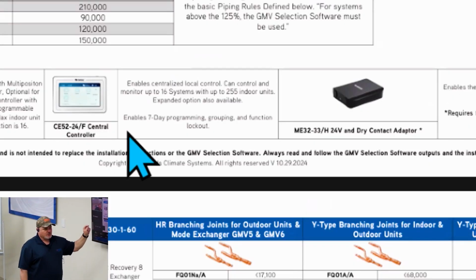Then with your daisy chain wiring between G1 and G2 between those 3, if you've already got those dip switches set, when you commission and start up those units, it's already going to automatically not duplicate addresses on your indoor units. So when you come back and hook up that central control or Cool Automation, it'll automatically be able to pull all those addresses in, because these are self-addressing, and you won't have a mode conflict. If you don't do that ahead of time, now we have to go back, shut everything down, reset the dip switches, and readdress everything. Now I can hook up central control. If you had just done that a couple of steps ahead of time, you'd have been fine.